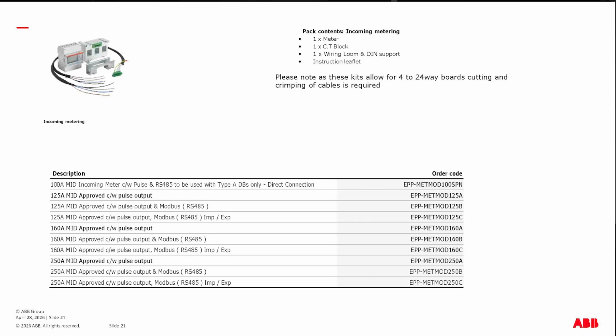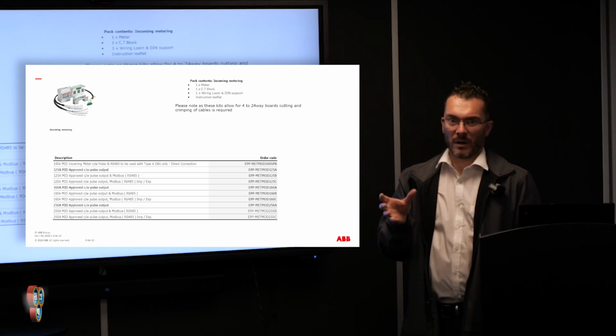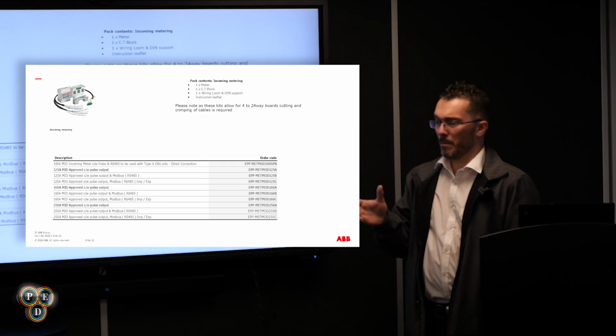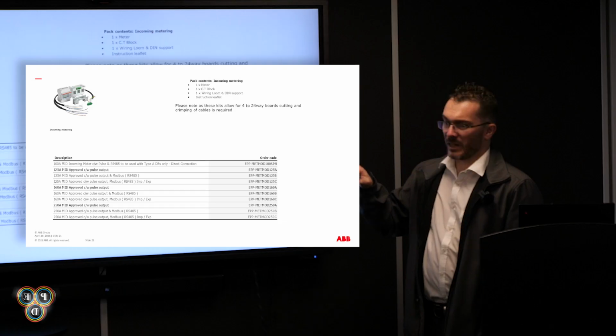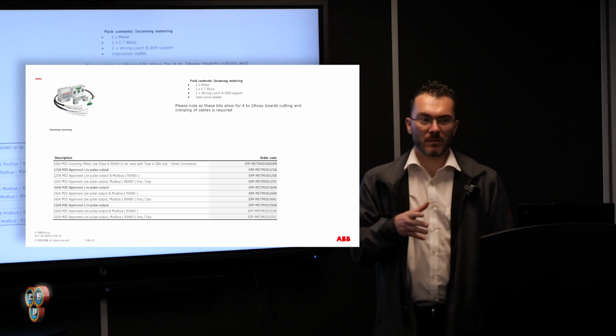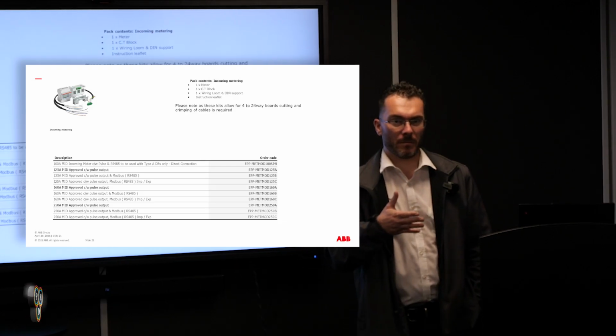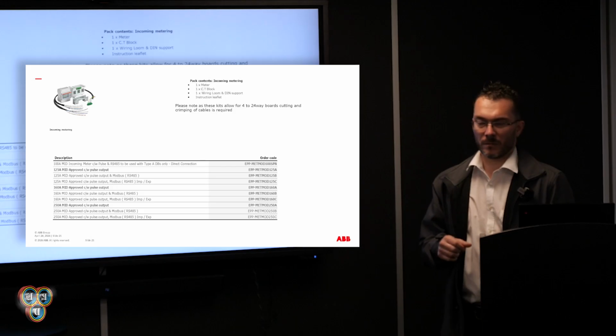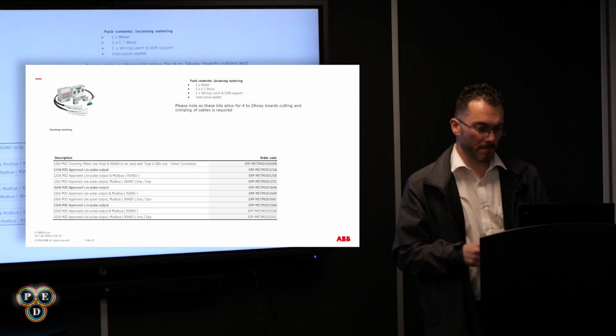The actual kits relate back to your size of incomer—125, 160, 250, as I've alluded to earlier. But the letter at the end, A, B or C, relates to the type of comms the device has got. A is generally just pulse, B is pulse Modbus, and C is pulse Modbus input/output. So if you've got solar panels feeding back to the grid, you can do your feedback tariffs and things like that.